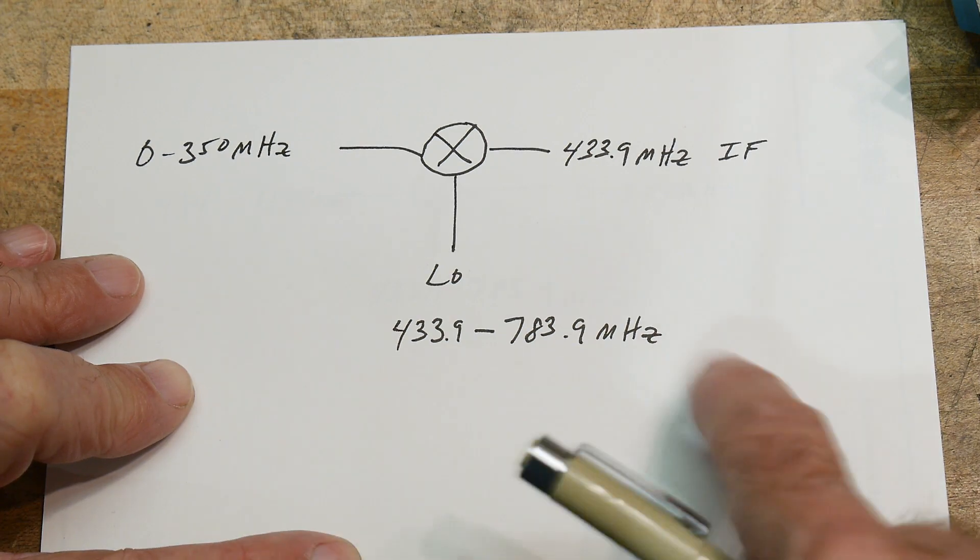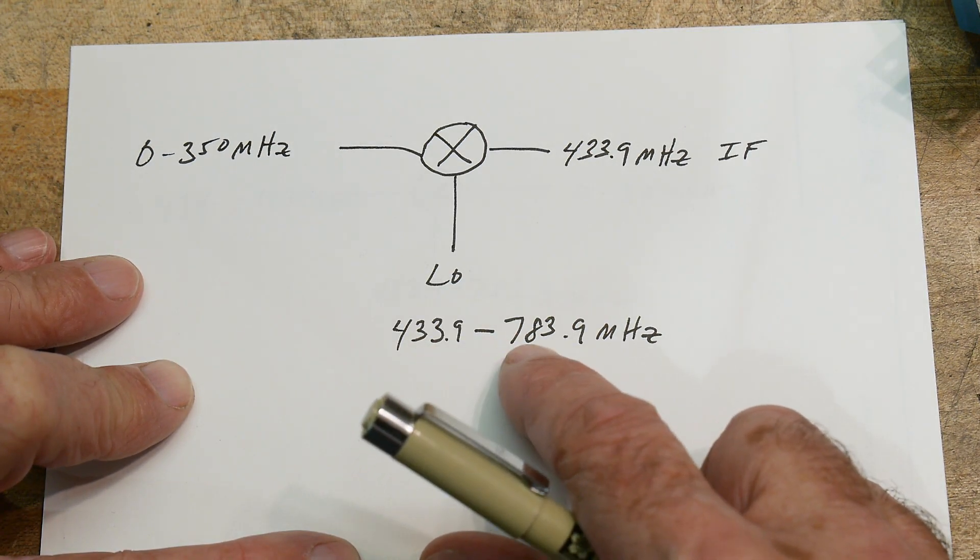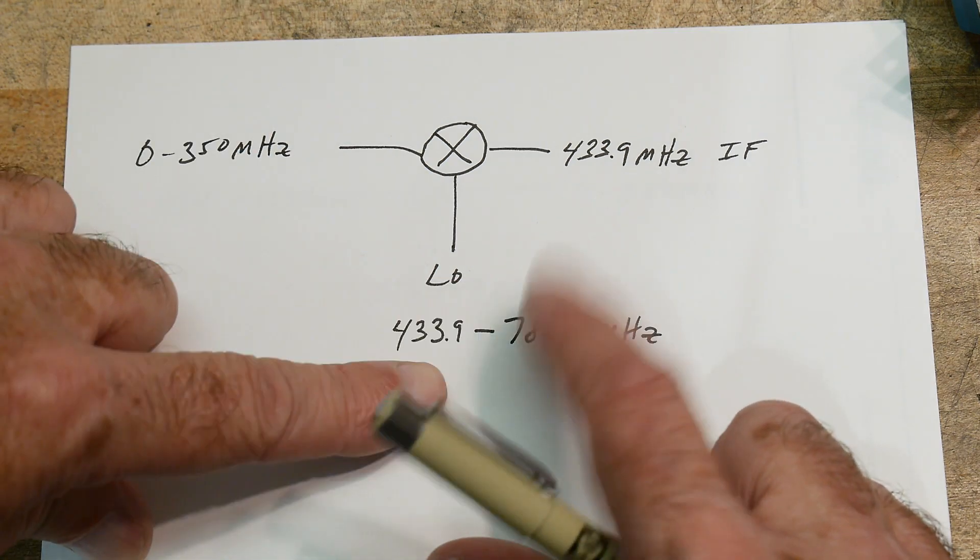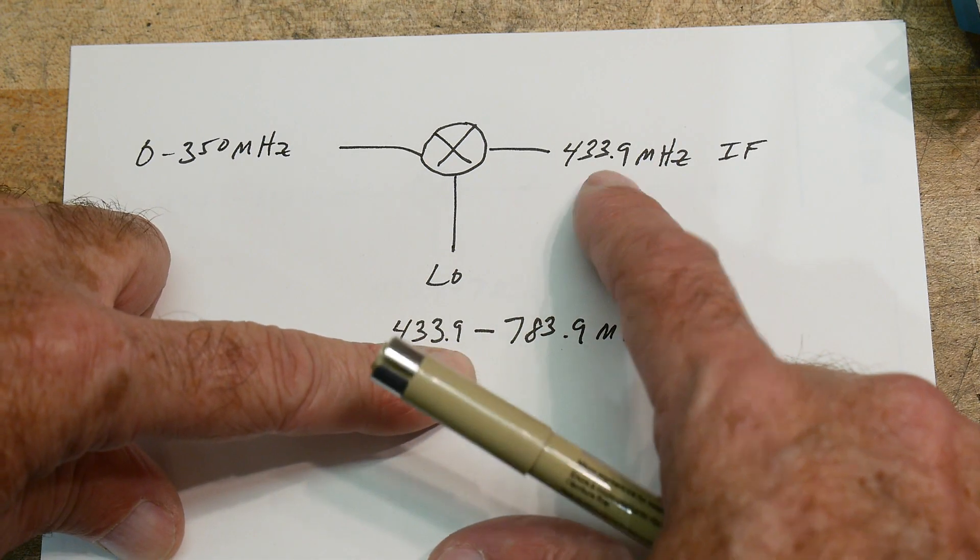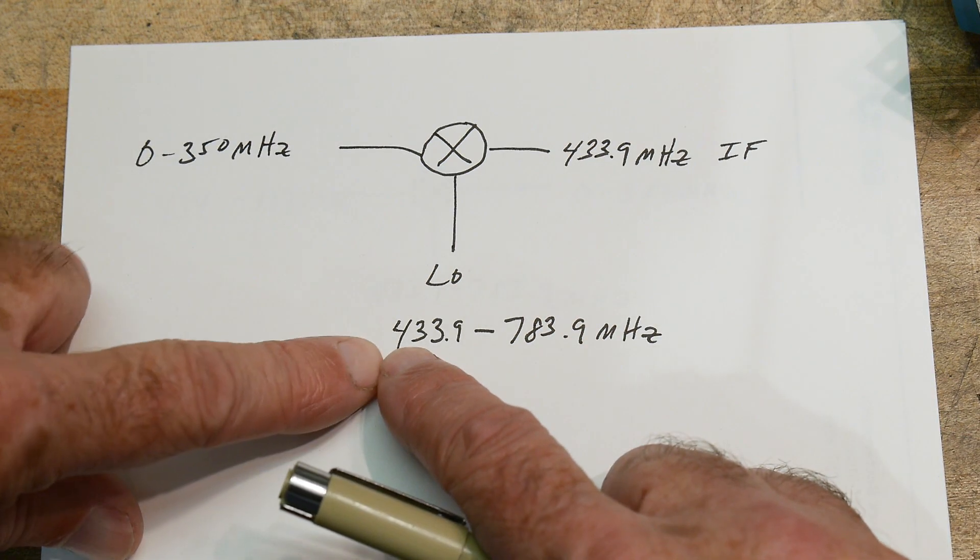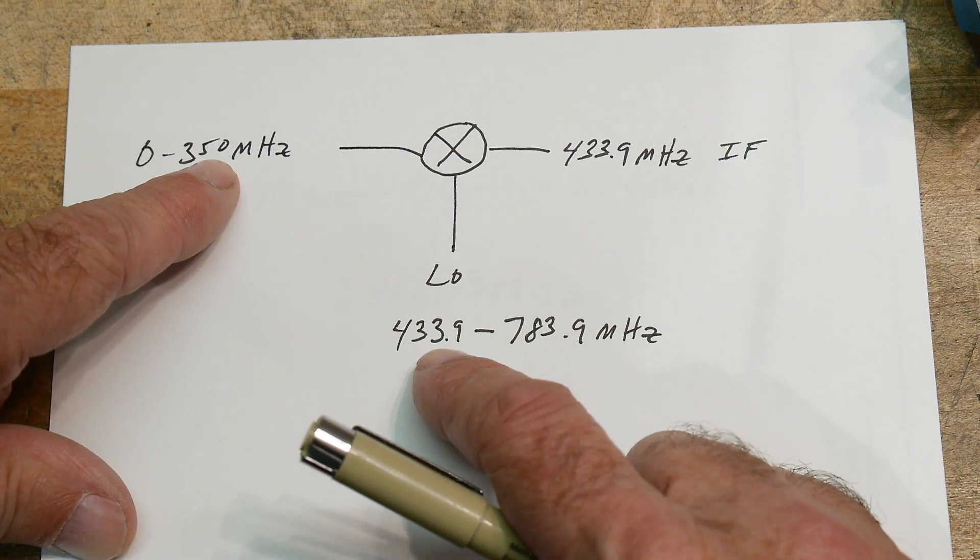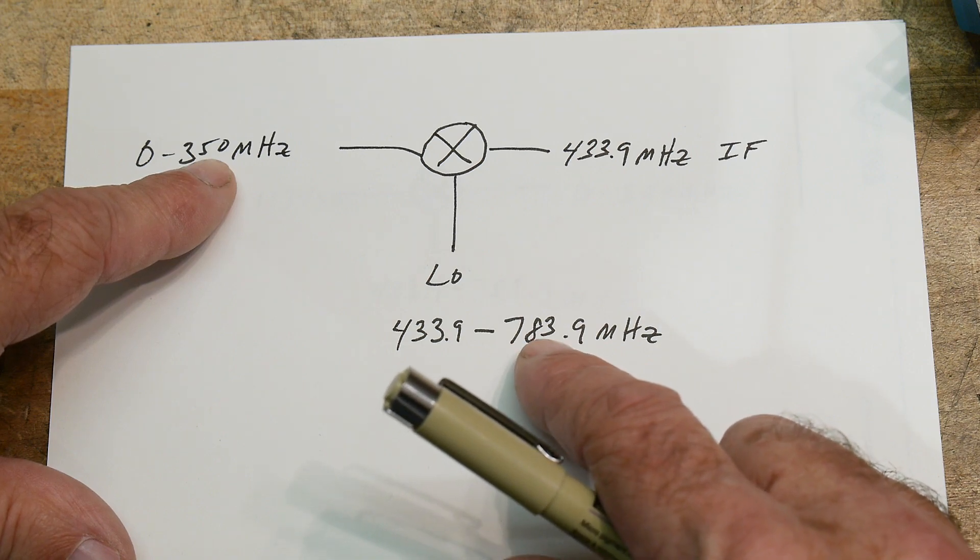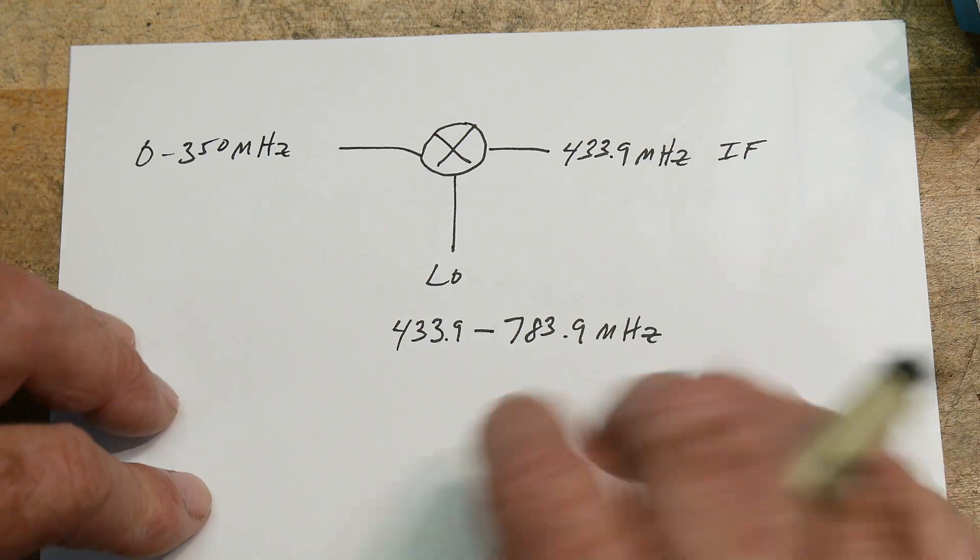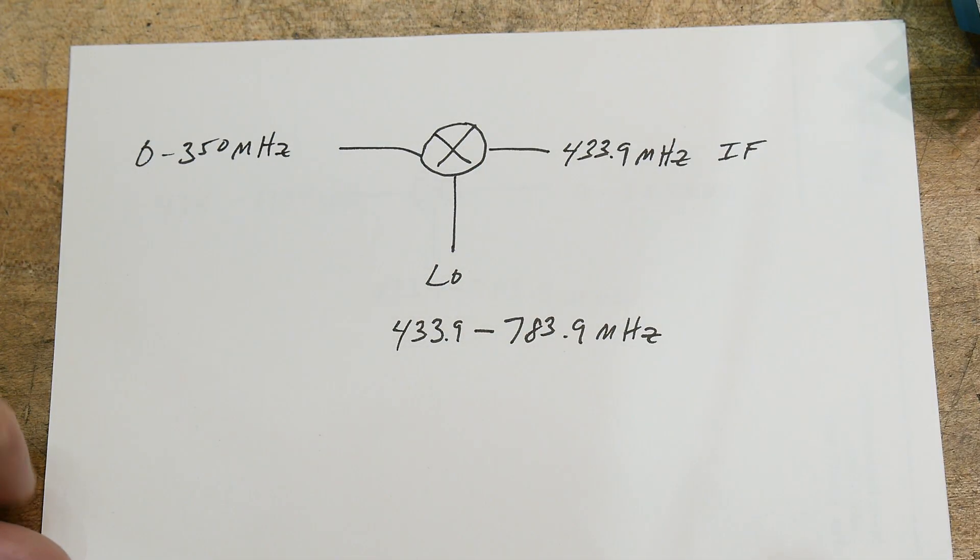That means that the LO, in order to measure 0 to 350 MHz, has to go between 433.9 to 783.9. It's going to take the incoming signal and increase it by this much, so it's going to add these two together and give you the intermediate frequency. So it's going to take 0 and add 433.9 to get 433.9, and it's going to take 350 and subtract that from 783.9. So it's not additive, it's subtractive.